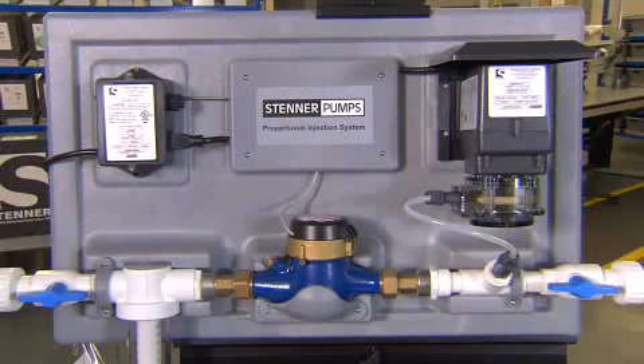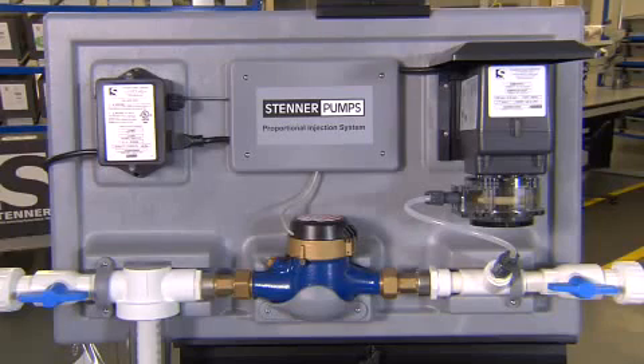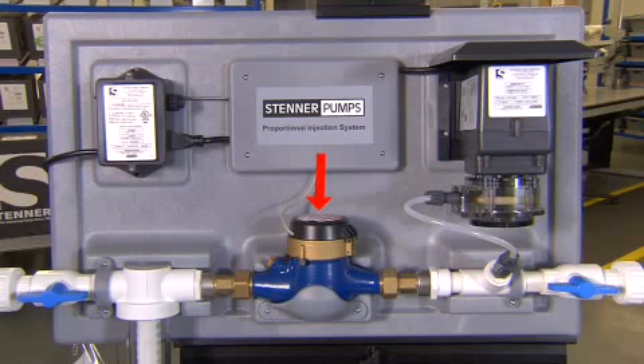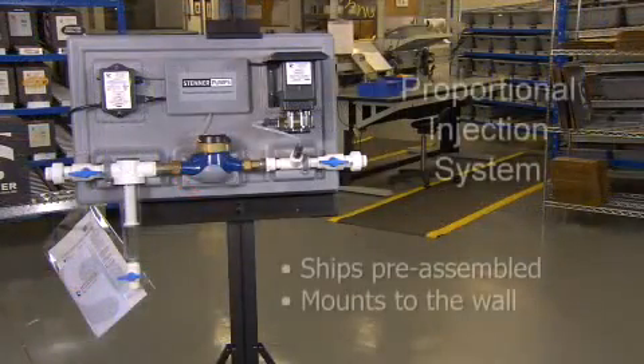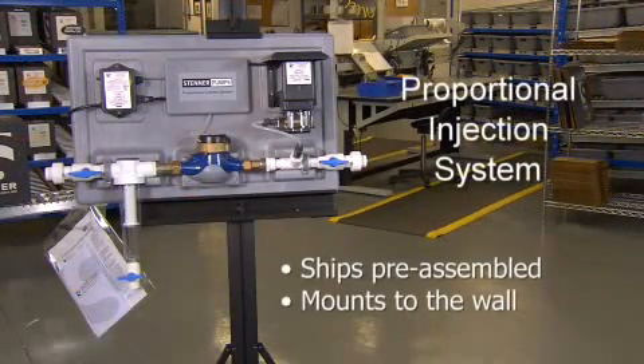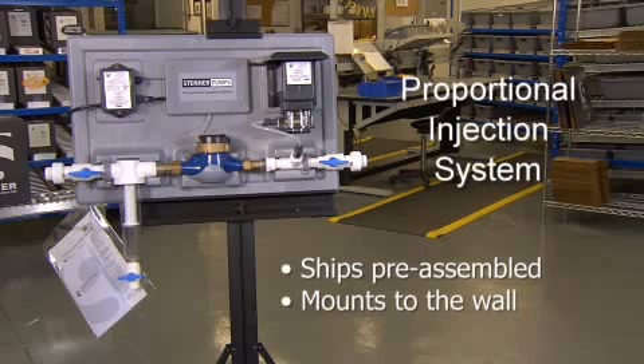The proportional injection system delivers precise dosing proportional to the water system's flow rate based on water volume. The primary components are the Classic Series single-head fixed output pump, a dry contact pulsing water meter, and the pump control module known as the PCM. The system is pre-assembled at the factory on a panel that conveniently mounts to the wall for timely installations and equipment accessibility. The system was designed for use with variable speed well pumps, livestock houses, irrigation, systems with demand based on backup wells, and applications with varying flow rates.